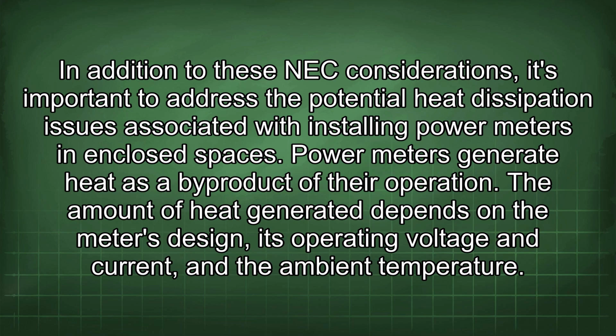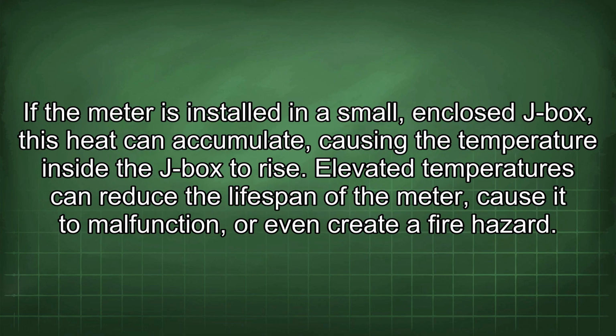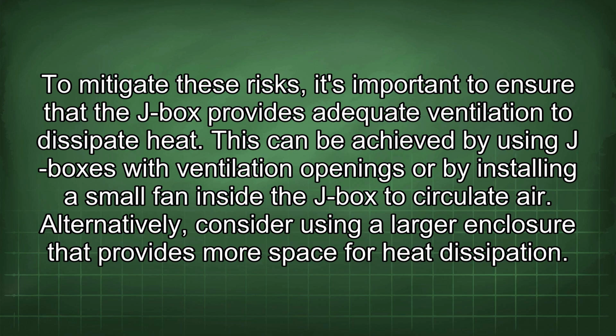In addition to these NEC considerations, it's important to address the potential heat dissipation issues associated with installing power meters in enclosed spaces. Power meters generate heat as a byproduct of their operation. The amount of heat generated depends on the meter's design, its operating voltage and current, and the ambient temperature. If the meter is installed in a small, enclosed J-box, this heat can accumulate, causing the temperature inside the J-box to rise. Elevated temperatures can reduce the lifespan of the meter, cause it to malfunction, or even create a fire hazard. To mitigate these risks, it's important to ensure that the J-box provides adequate ventilation to dissipate heat. This can be achieved by using J-boxes with ventilation openings or by installing a small fan inside the J-box to circulate air. Alternatively, consider using a larger enclosure that provides more space for heat dissipation.